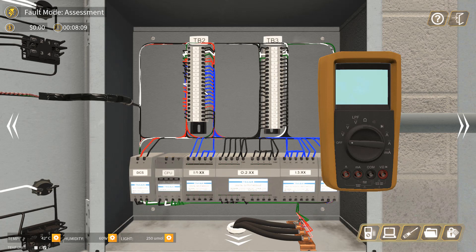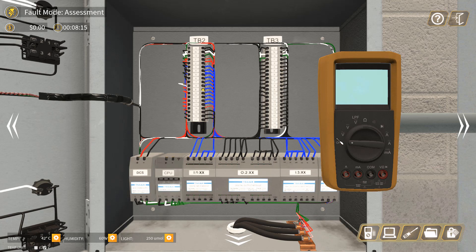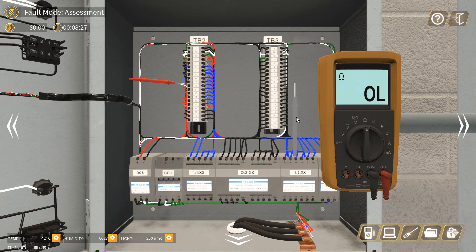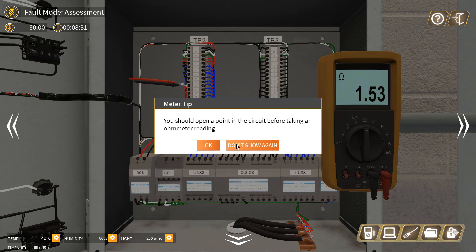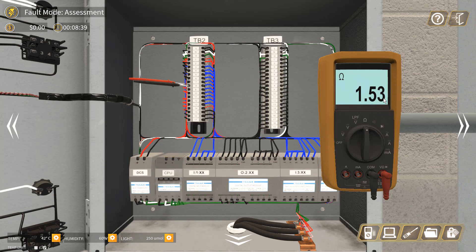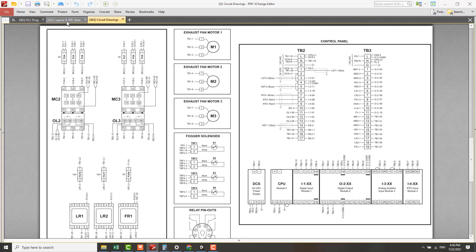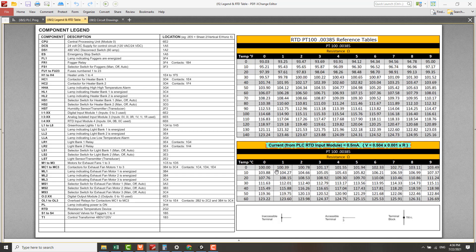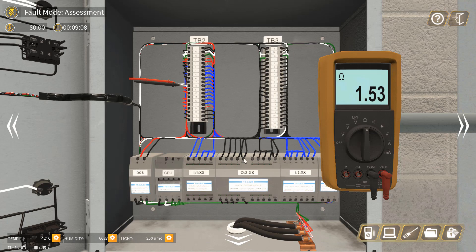Use a screwdriver and then remove all the wires so that we can measure resistance across the load. Now the resistance is 1.53 ohms - this is not correct. It should give you around 100 ohms because RTD using PT100, platinum 100, meaning 100 ohms at 0 degrees. The reading should be around maybe 80 plus, around 100 plus or minus 30, maybe around 70 to 130. It should not be lower than 2 ohms. The 2 ohms usually means short circuit. So we can go change the RTD on site.